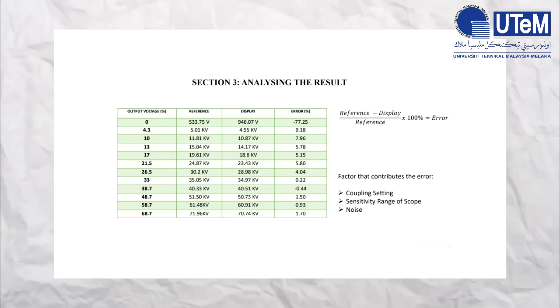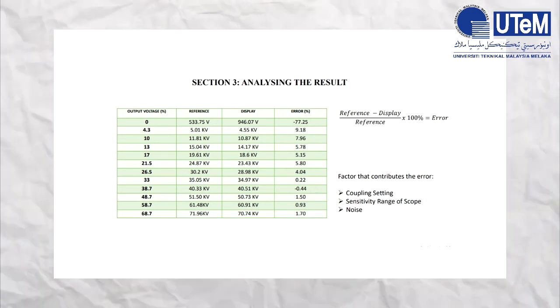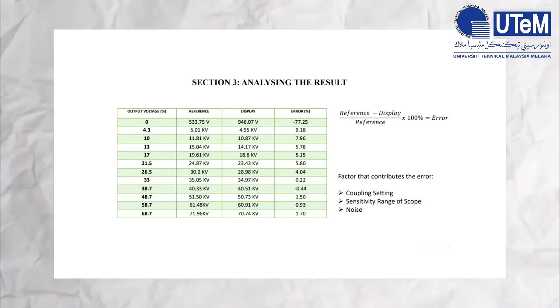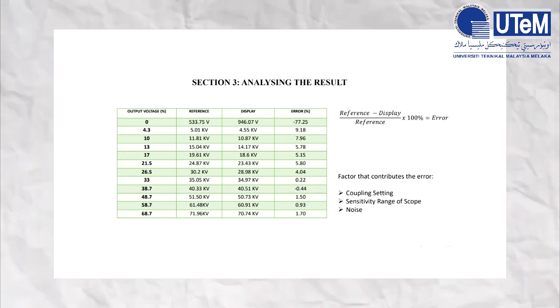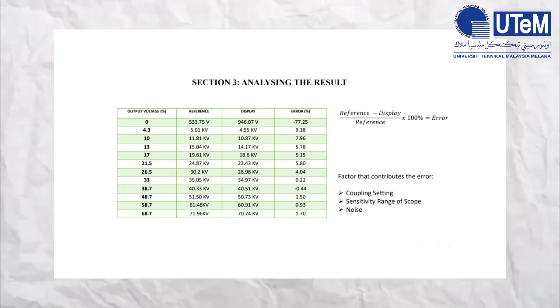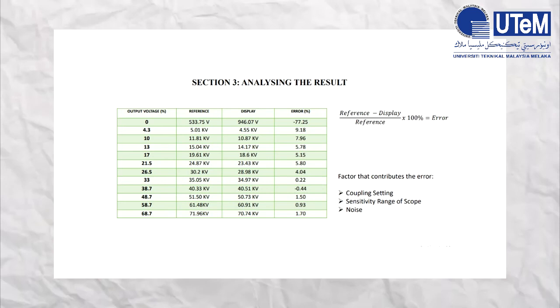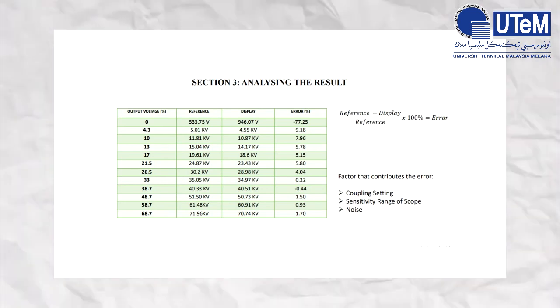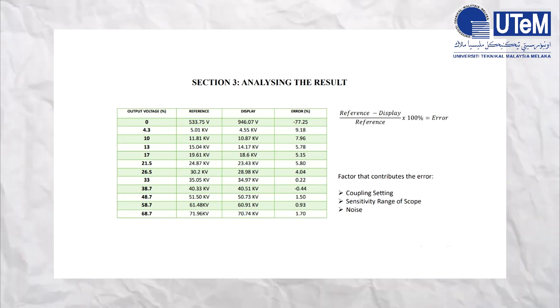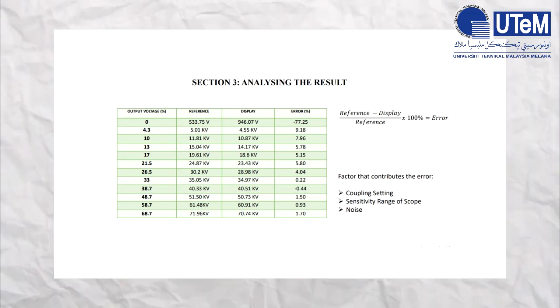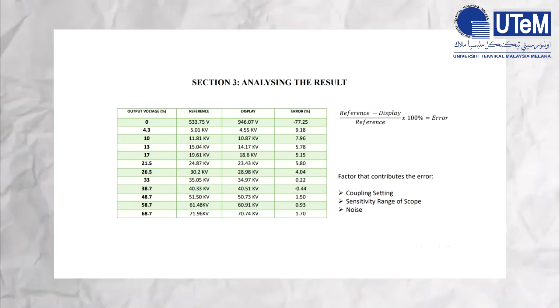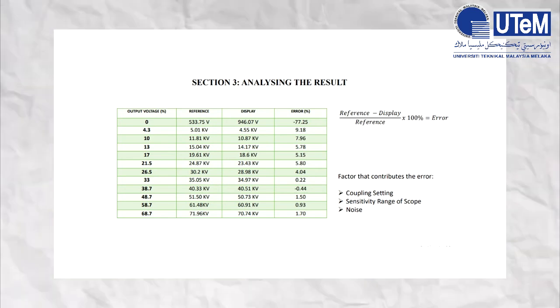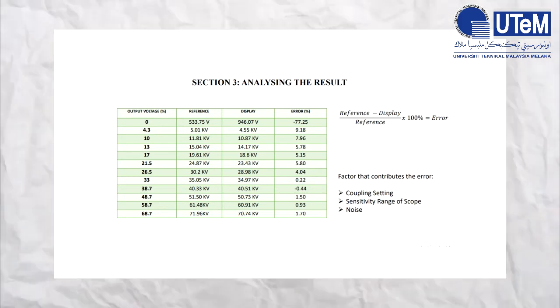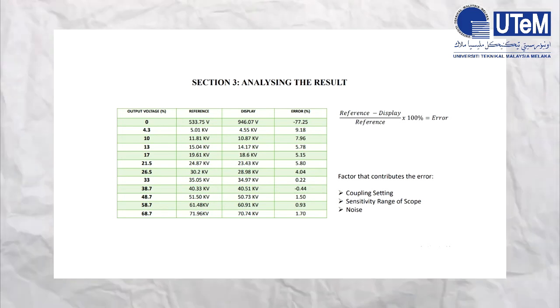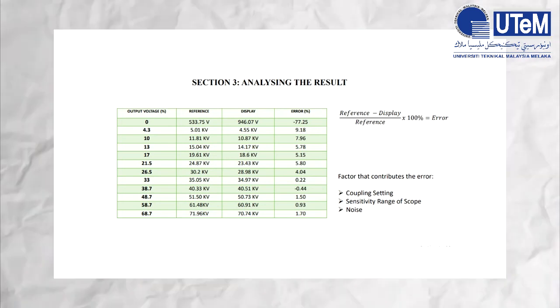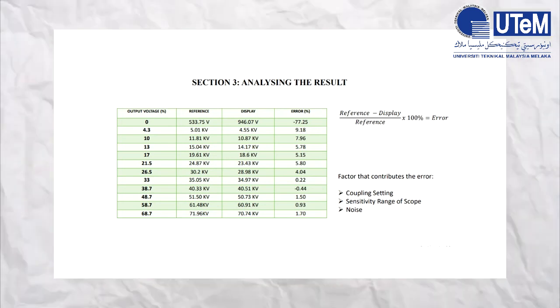We have set AC for the setting. AC coupling means that it will filter out all of the DC components. It switches in a high pass filter on the channel input signal. The sensitivity of the range also contributes to the increase of error. We have set the value to a certain level where it makes the sensitivity more accurate. Last but not least, noise also affects the difference between the display and reference values. One example of noise is the noise that comes from the power supply.